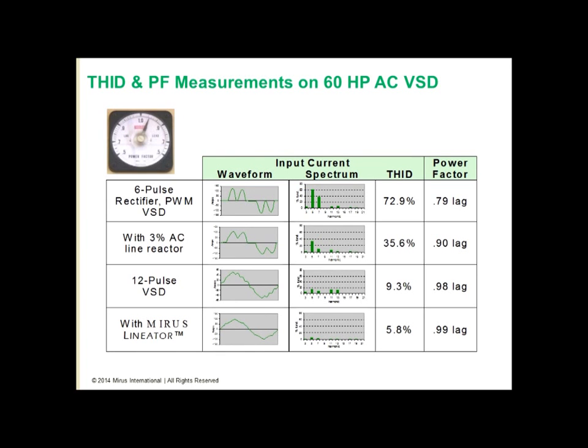The final row shows the effect of a lineator being applied to the 6-pulse rectifier in the first row. We now have an almost sinusoidal current waveform. The current harmonics are virtually eliminated. Current distortion is dropped to less than 6%, and power factor now is near unity.